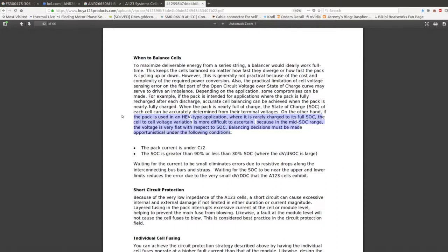If you're making battery banks, you need to be aware of this, and you need to balance your packs appropriately. If your state of charge isn't charging right up to the limit... like if it's lithium ion and you're charging the entire bank up to 4.2 volts per cell, and you're out of balance without a balancing mechanism in place, you're going to be at that point of danger every time you charge the pack.